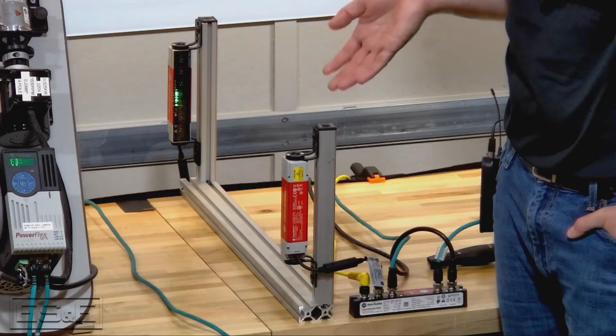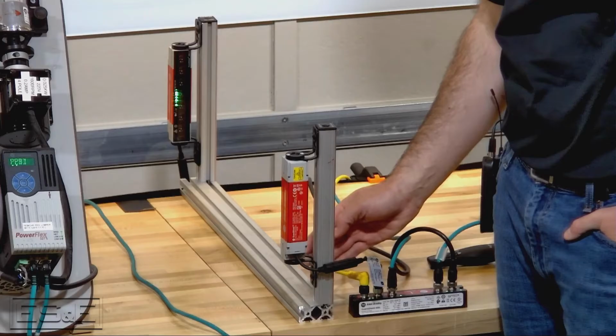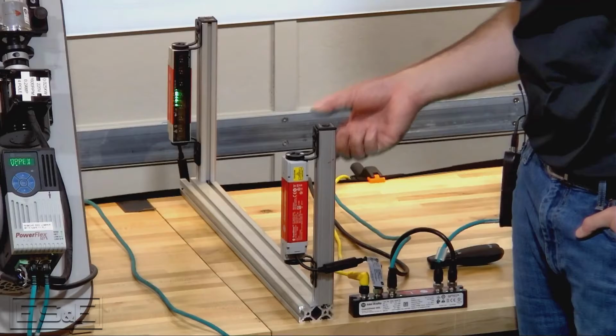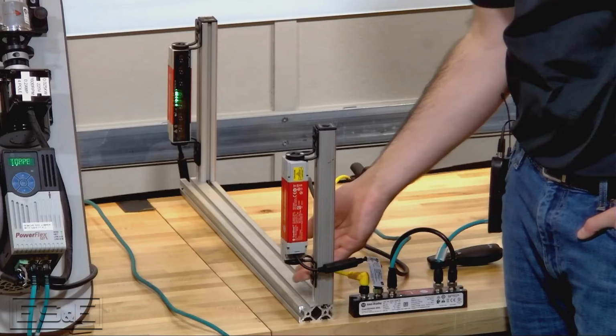That's important to know for muting applications. If you have an application where you have something that's going to pass underneath and you want to mute that segment, you wouldn't be able to have these mounted upside down, for instance, because then you'd break that synchronization beam, right?